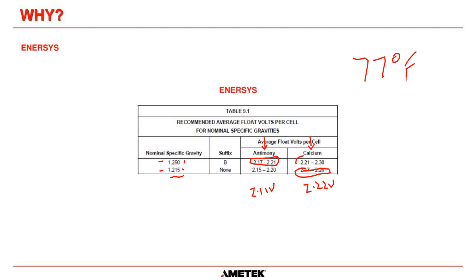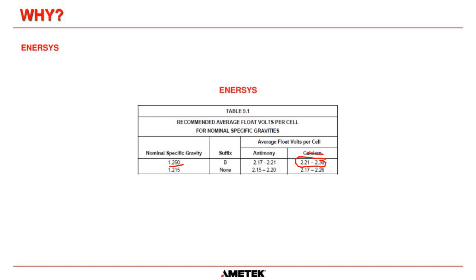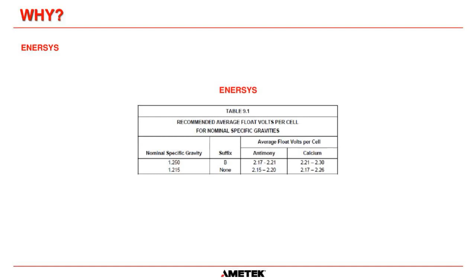But this one here is the most popular, is where we get the 2.25 volts from. And that is a 1.25 specific gravity with calcium plate grid. And that works out, the average in the middle is 2.25 volts per cell. Now remember, that's for Enersys.